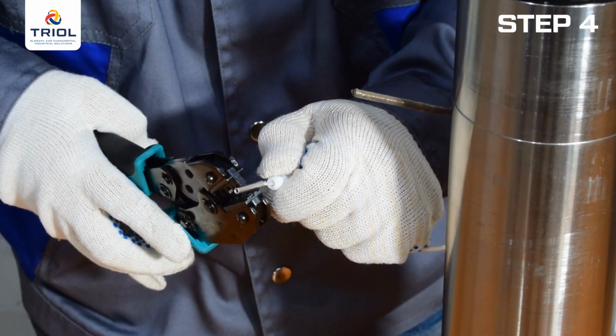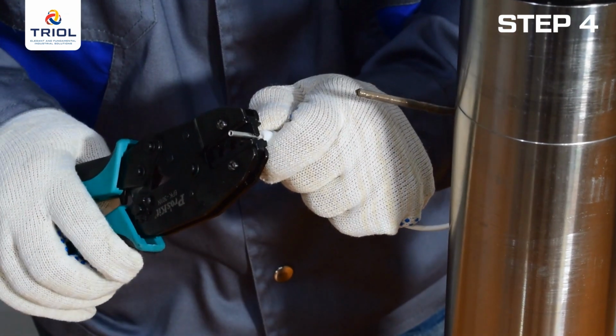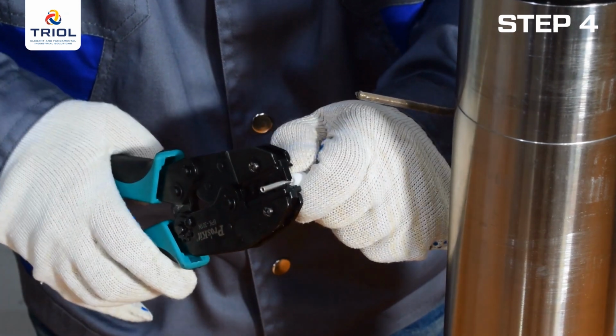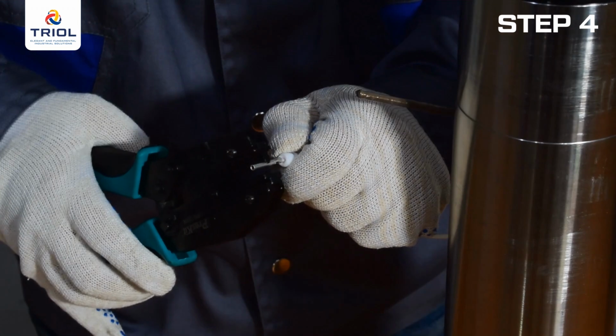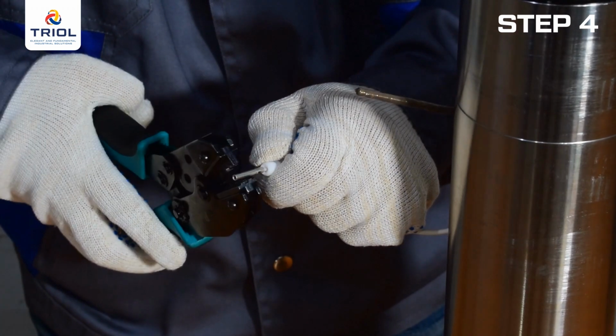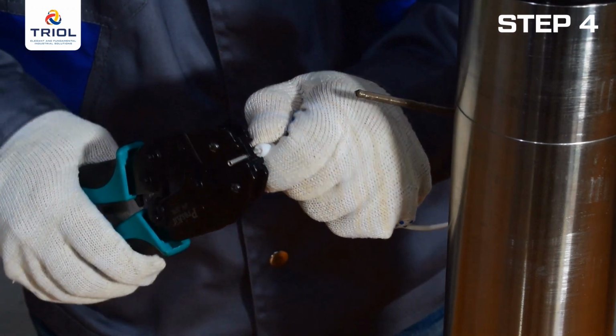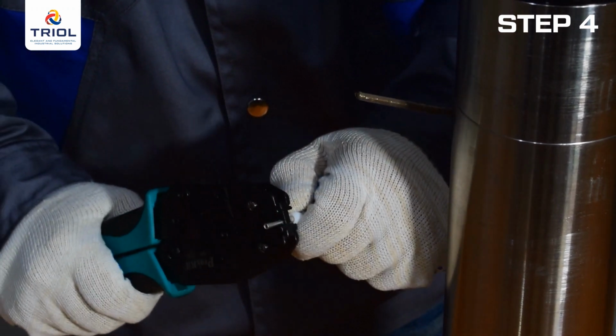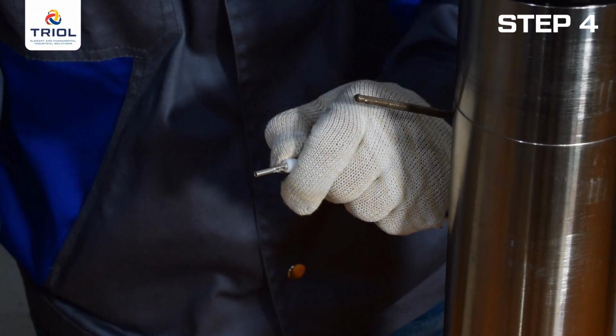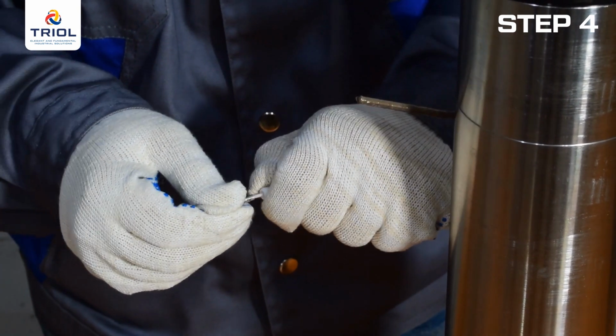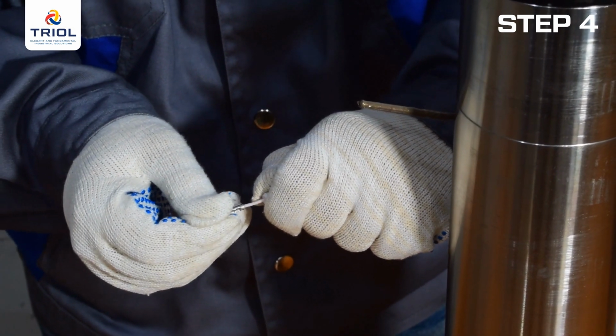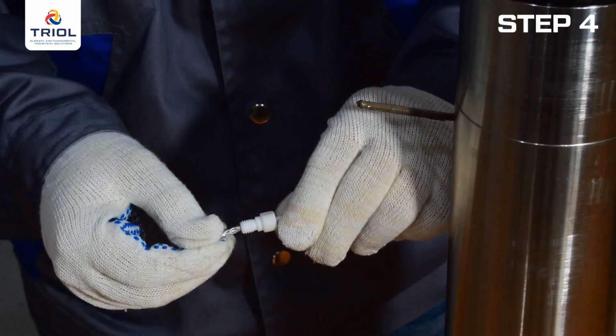Fix it in your hands and slide the sleeve on the stripped free end until it stops. Crimp in 2 places using crimping pliers. Crimping points are at the beginning of the sleeve and at 0.08 inches or 2 millimeters from the special groove in the sleeve itself. Pull the wire and the sleeve in different directions. Make sure they are firmly fixed and connected.